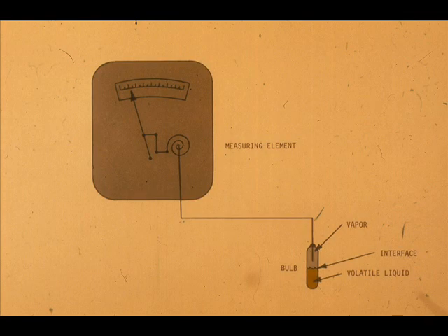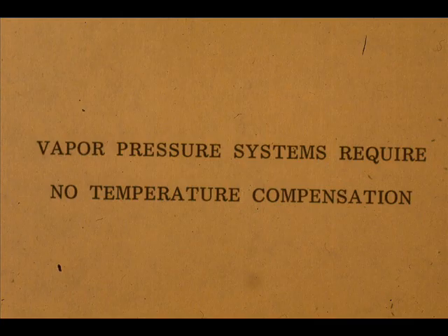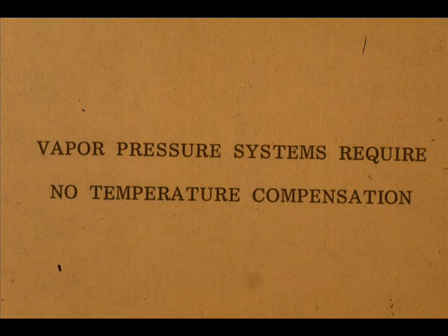Unlike the other systems, which measure average temperature, the vapor pressure type measures the temperature at the interface between the liquid and the vapor. This is why the vapor pressure systems require no temperature compensation mechanisms.